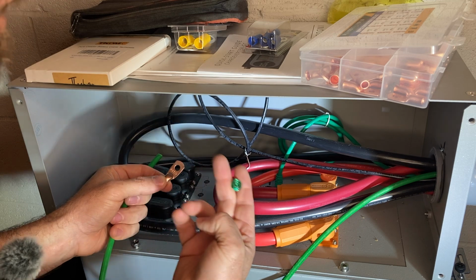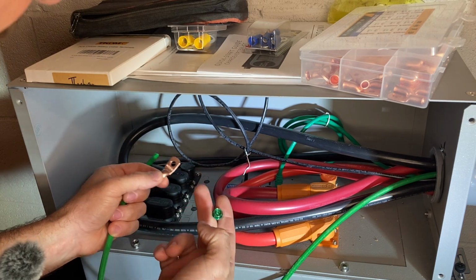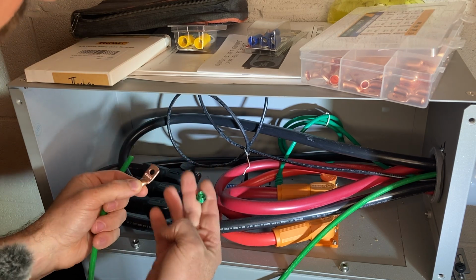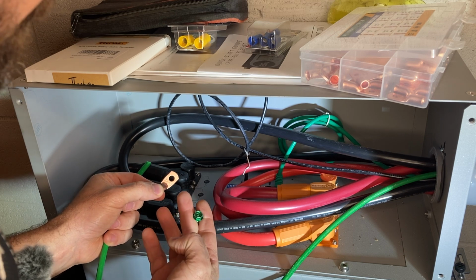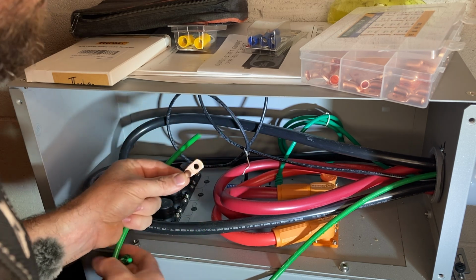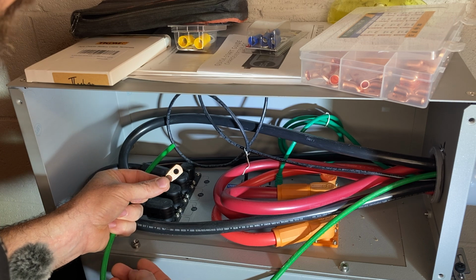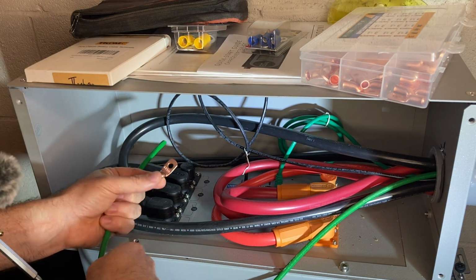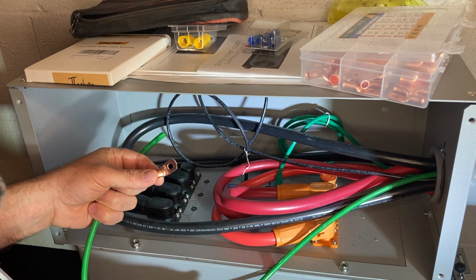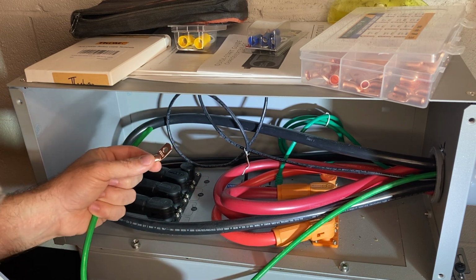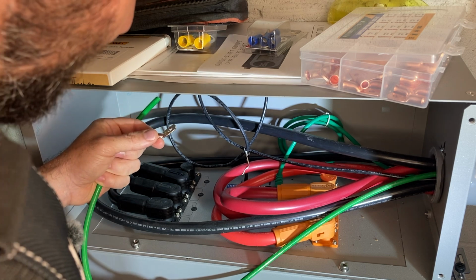Alright, to connect the equipment ground to the ground screw on your battery, looks like in my case I've got number 6 wire, so I'm going to use a 6, 1/4 inch lug. I guess the 1/4 inch is the important part depending on the equipment ground you use. In my opinion, 6 gauge should be more than sufficient.